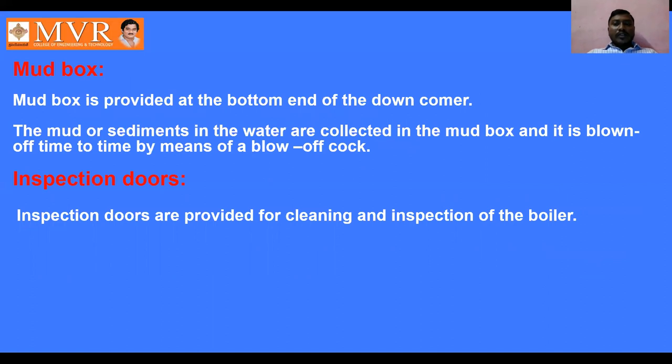And a mud box is where the sedimentations formed in the boiler are collected through this downtake header, and by using this downtake header, these sedimentations are removed through a blow-off cock. Inspection doors are there in the diagram, which we can observe. By opening these doors, we can enter into the boiler for cleaning and inspection purposes.